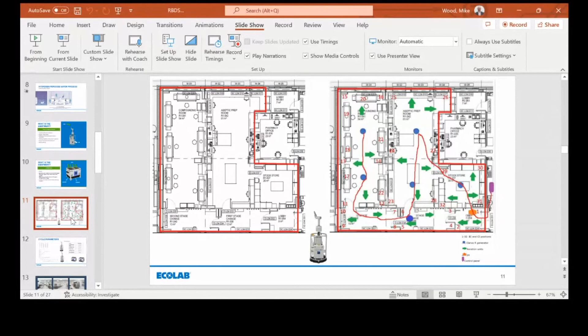The parameters for this were very straightforward: a 10-minute conditioning time, which is when our Claris vapor generators come up to heat, raising the heat. Once they reach heat, we went into our gassing stage, which took 37 minutes. The dwell time, where we achieve full kill, was 20 minutes, and aeration took 125 minutes. The amount of H2O2 injected was 4,216 grams.